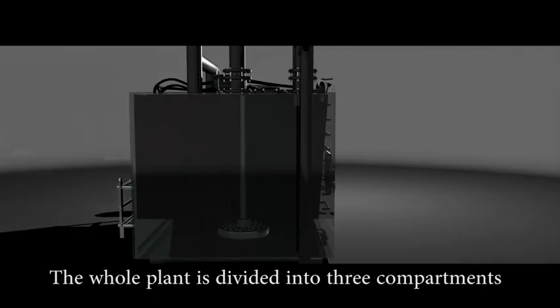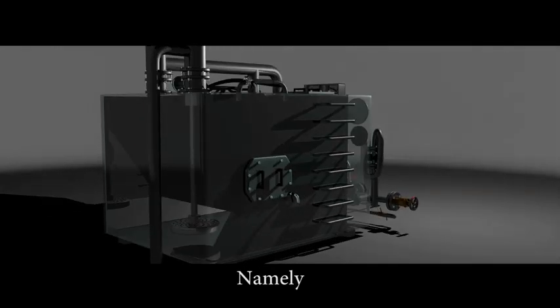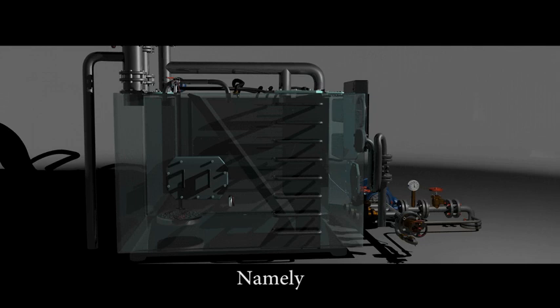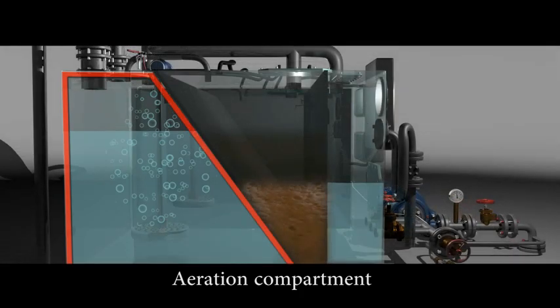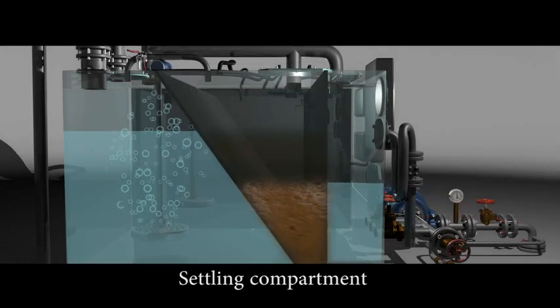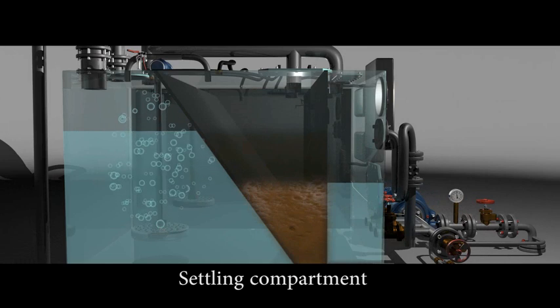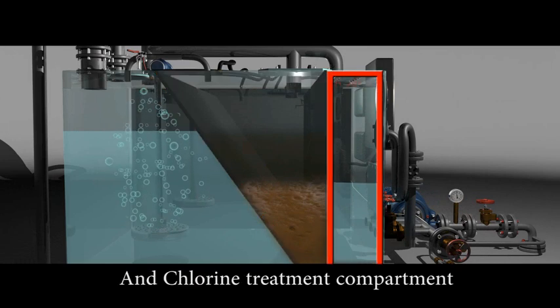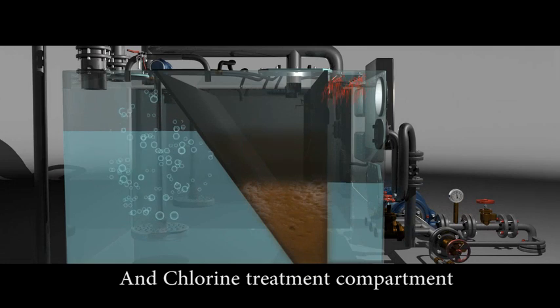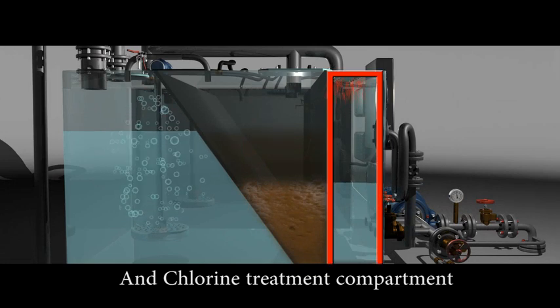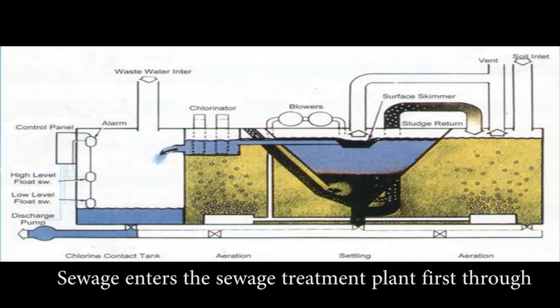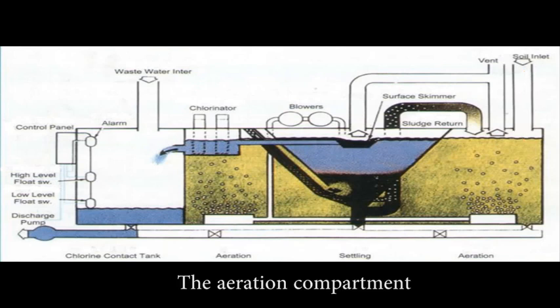Choking of strainer, baffle plates. Choking of activated sludge return line. Choking of bubbling tube. Only approved cleaning agents to be used in the toilets, as strong chemicals, such as bleach, can kill the bacteria necessary for breakdown of the sludge.